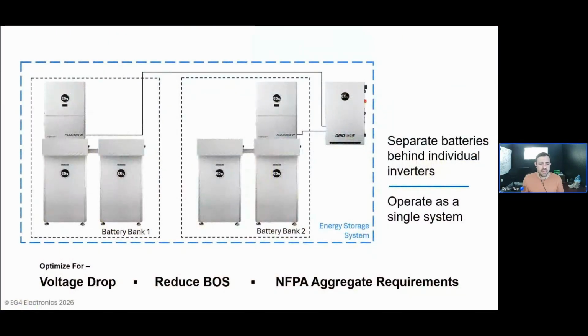Now, further extending that, you can even do things like separate batteries behind individual inverters and operate those inverter and battery subsystems, as I'll call them, as a single system overall. So what we can see here is essentially a site that, for whatever reason, whether it be just physical constraints on the site with not much space or restrictions from NFPA, has a situation where there's really only room for 2 batteries in a given location.